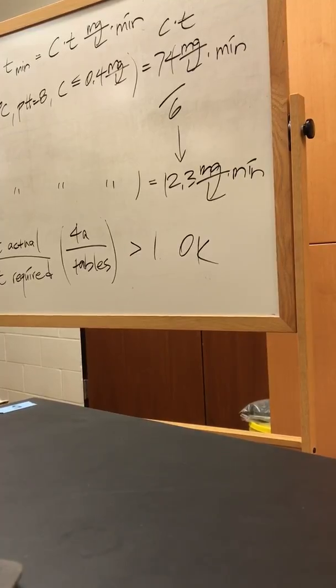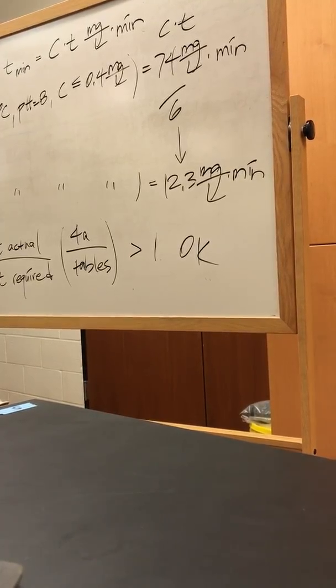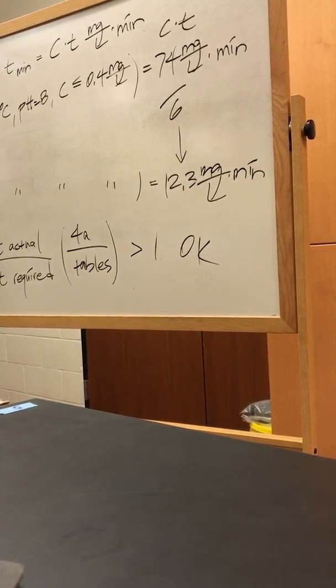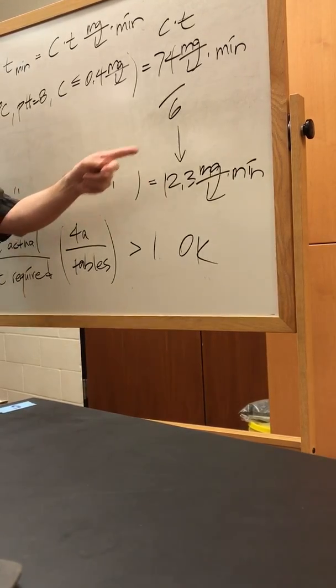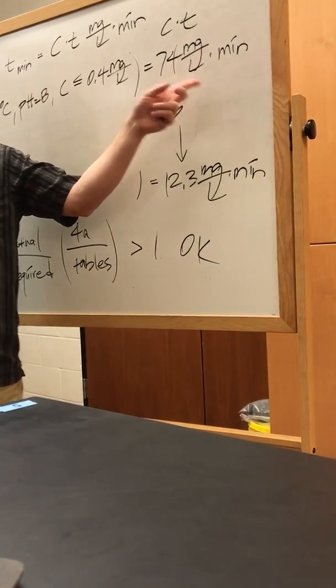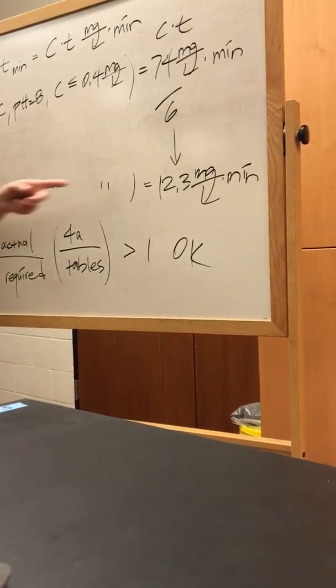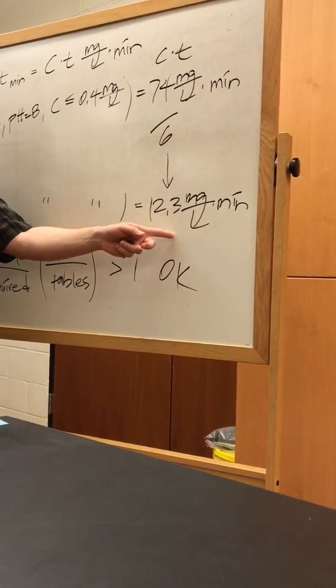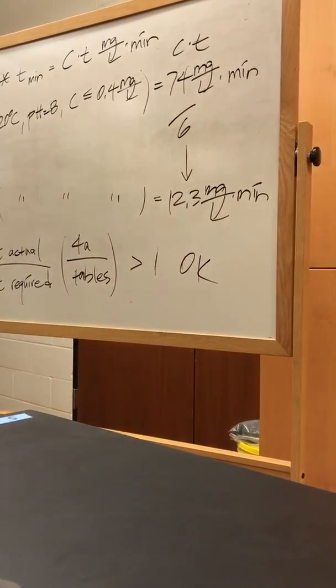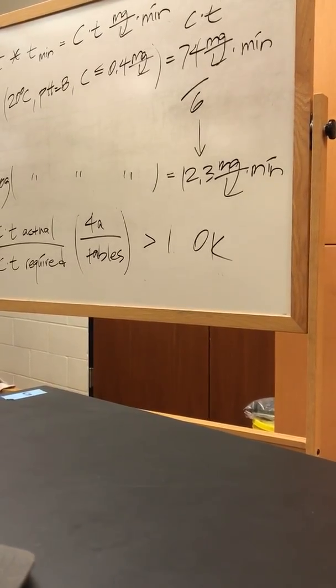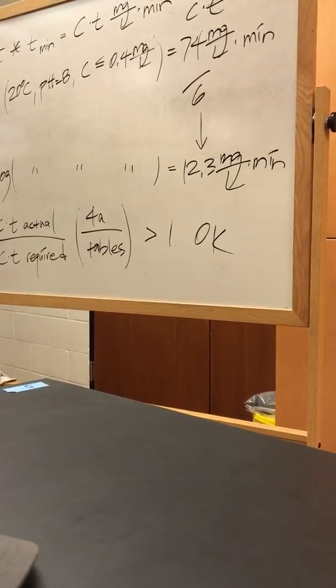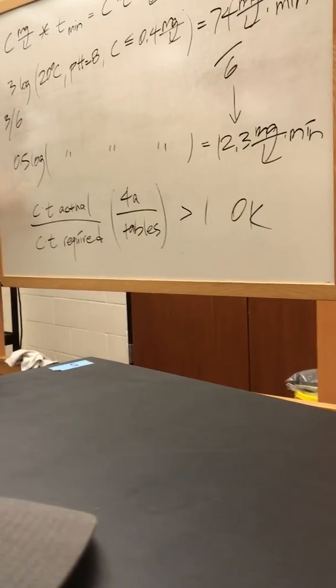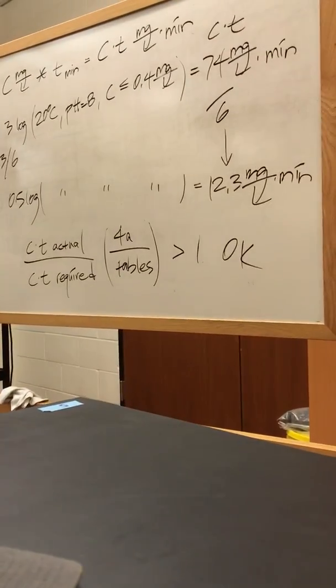The ratio from 3 to 0.5 is 3 divided by 0.5, which is 6. So, because everything else is the same, all you do is divide your CT that you got for 3 log removal by 6, and now you've got a CT for 0.5 log removal. Does that make sense?